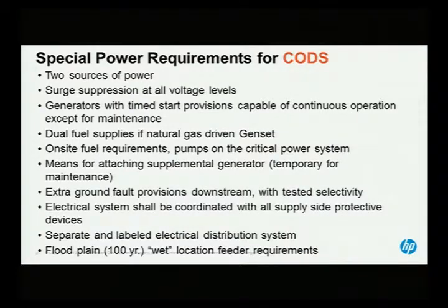You have to have a means for attaching a generator so you can do maintenance on the generators that are on site. In other words, you have to have the ability to roll up a generator, plug it in, and be able to operate off that generator, have that be your standby generator while you do it. Think Tier 3, right?